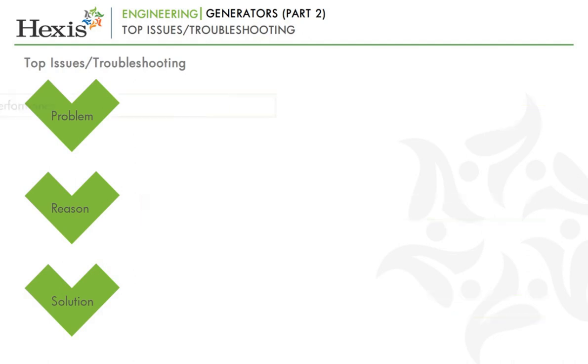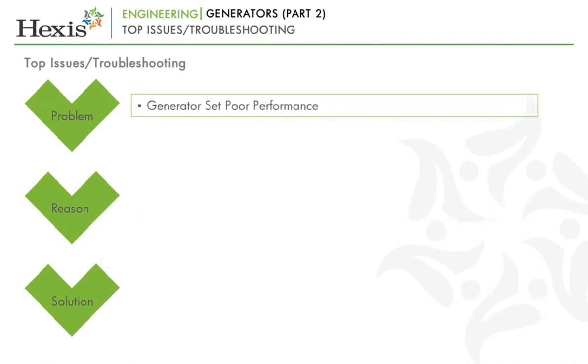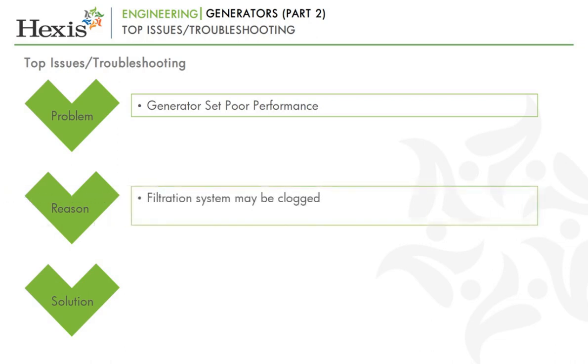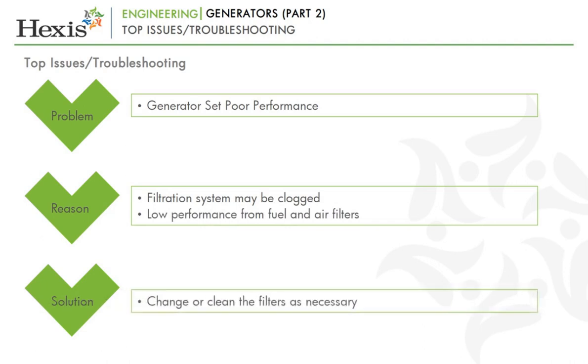Problem: generator set poor performance. Reason: this is due to filtration systems clogged. Fuel and air filters will retard performance. Solution: change or clean filters as required.